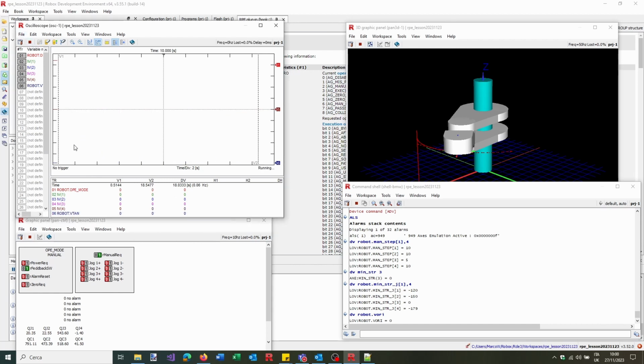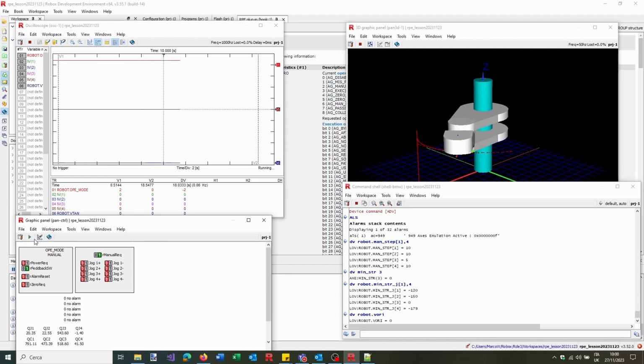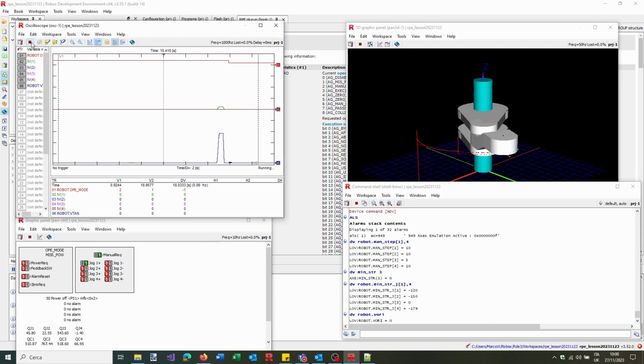Now let's see something more interesting. Let's, for example, do a mistake. Let's make this be stable. So now, while I press it, it will remain pressed, and then we try to make a fast stop. So I press it and close it like this. Now let's check. Here we can take a look that until this point we were making a smooth ramp due to the manual.